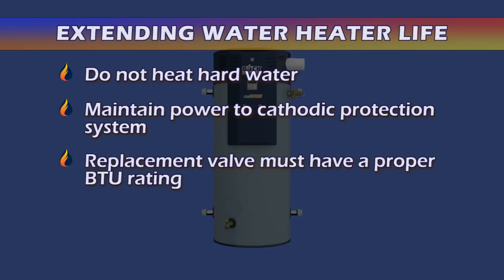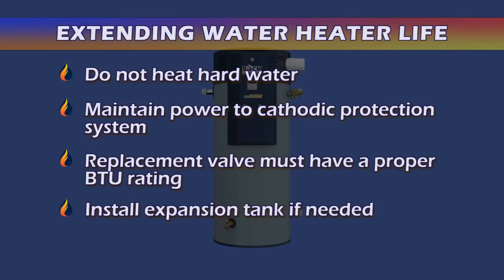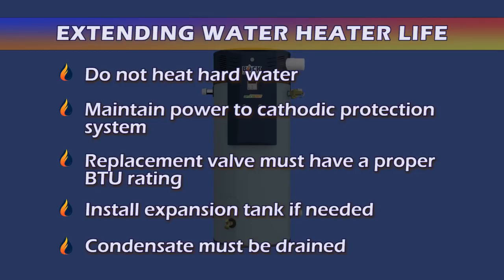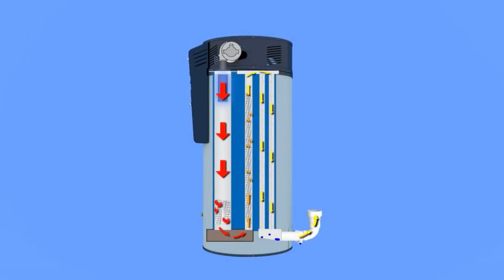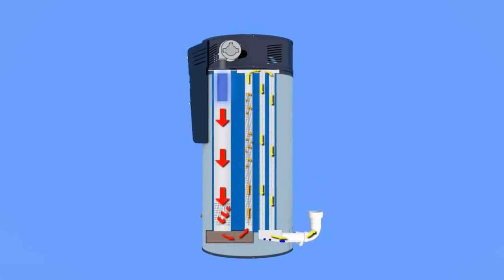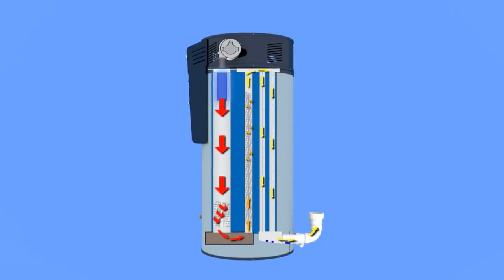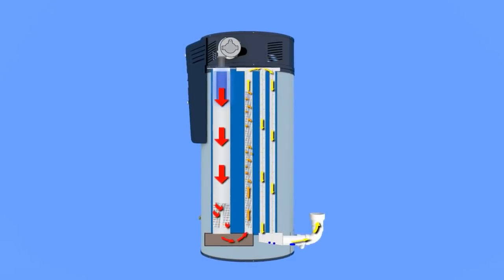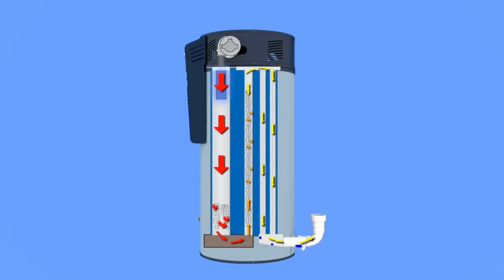Third, if the temperature and pressure relief valve requires replacement, it must have a BTU rating equal to or greater than the BTU rating of the water heater. Fourth, be sure an appropriate expansion tank is installed to control thermal expansion when needed. And finally, the optiTHERM is a high-efficiency gas water heater and produces condensate which needs to be drained. A supplied condensate trap is installed in the exhaust vent, and an optional condensate trap can be installed in the intake to prevent condensate from collecting in the vent or entering the burner.